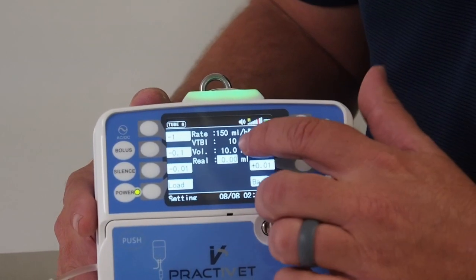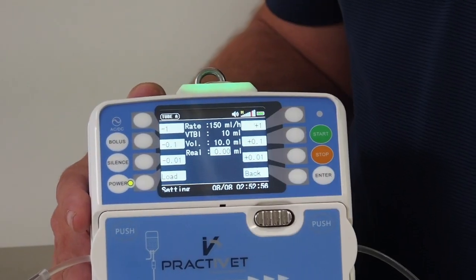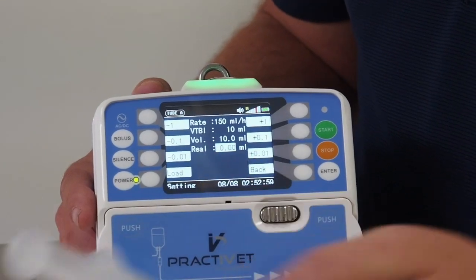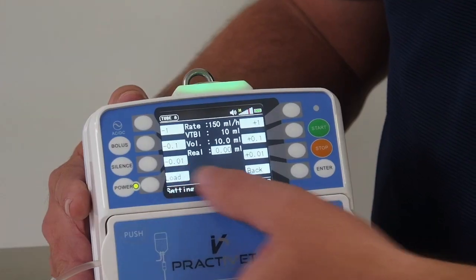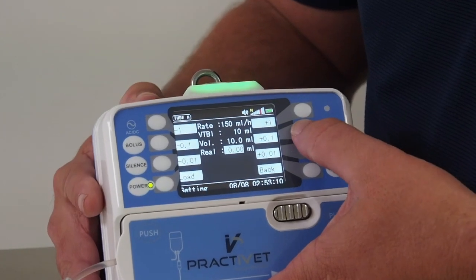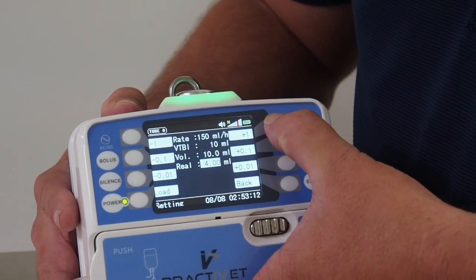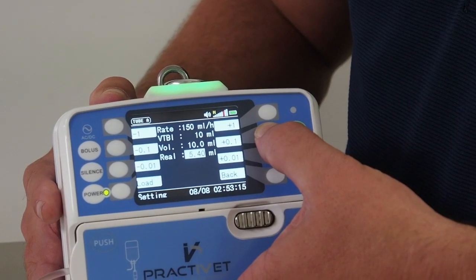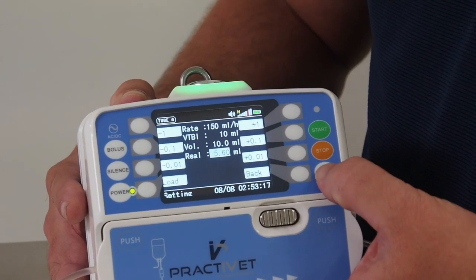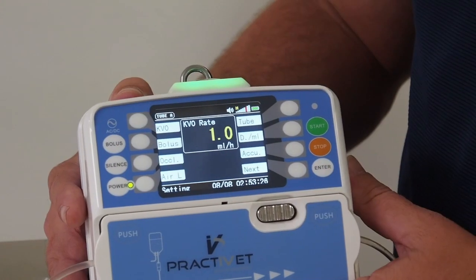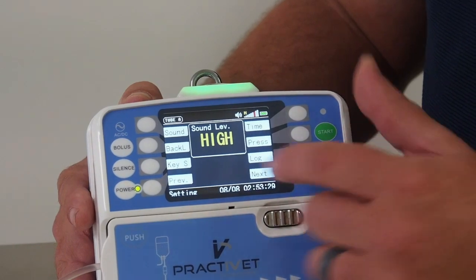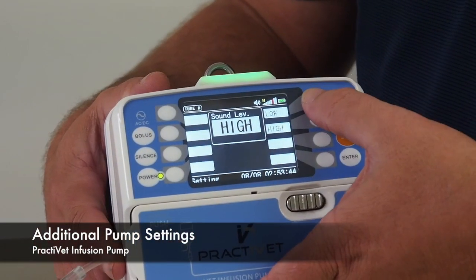Okay, once the pump has run through its calibration mode, as you can see now that the pump is pumped 10 mils, we want to now program what the real is. The real is what it actually pumped into the syringe, and as I can see here, it looks like it's at about 5.6. So I will program the pump. I'm going to press up 5.6 and enter. Now this pump is 100% accurate with this light. Then I'm going to back out of that setting, hit next. I can turn the sound to low.